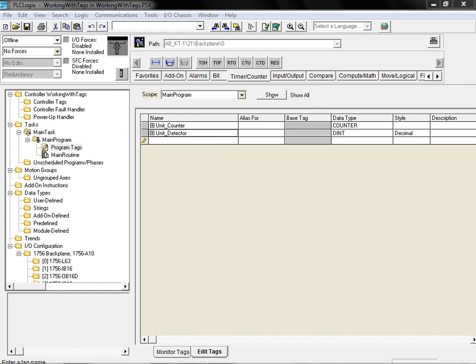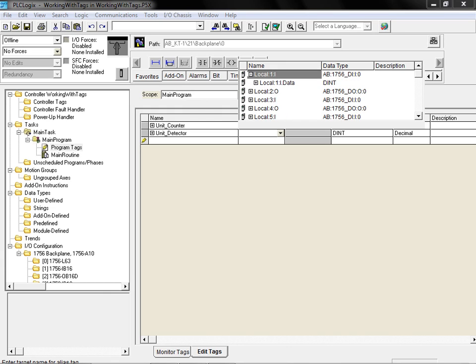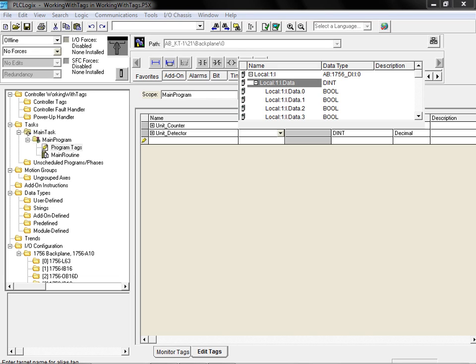To define the alias tag, select the alias for field. Next, click on the drop down arrow to bring up the listing of available tags. In this instance, our field device is connected to the slot 1, bit 2, input rack location. Expand the controller tag associated with the slot 1 input module and select the bit 2 specific tag.